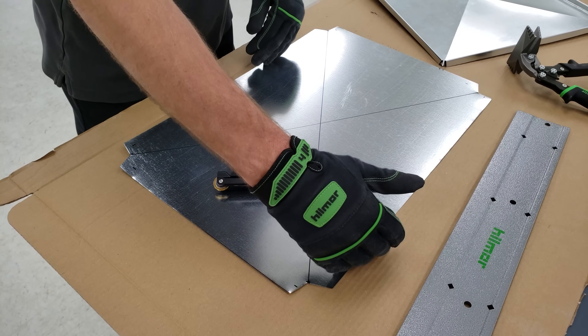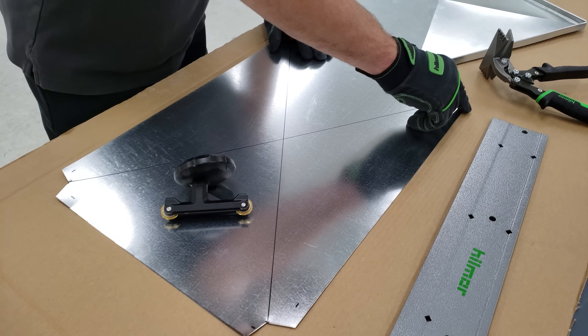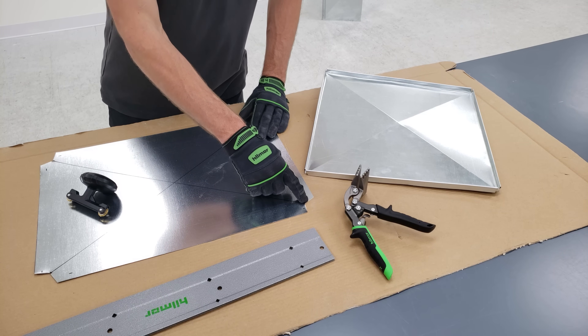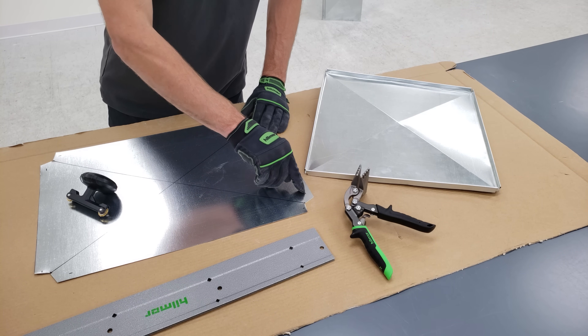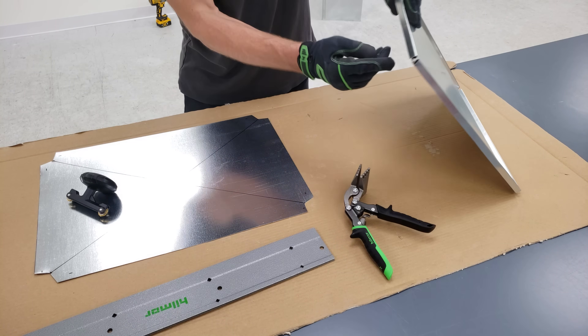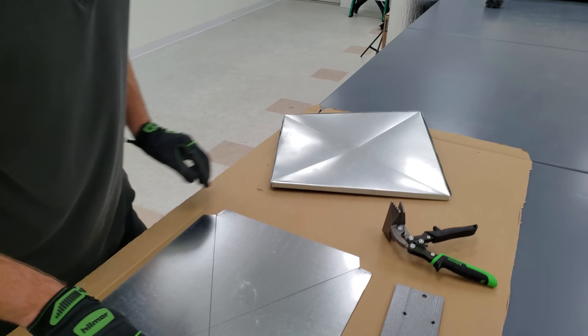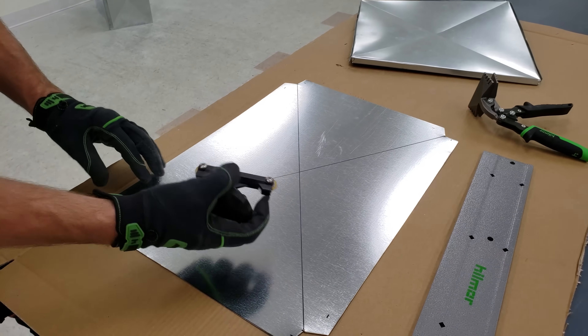We've cut out our end cap, and remember this is one inch passed on both sides. What I did is I notched in with my tin snips one inch in both directions. I've also marked a half inch because that's going to be our bend for our hem right here for our end cap. We're also going to bend our cross breaks right here using our pocket brake, so we're going to go ahead and get started with that.